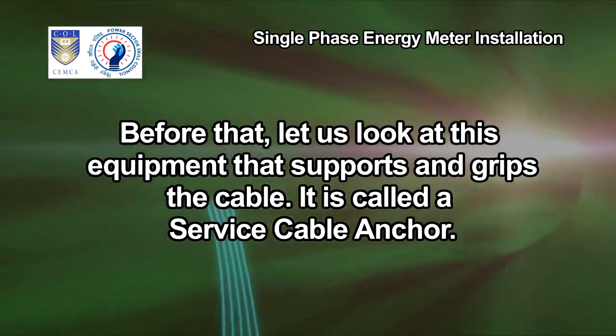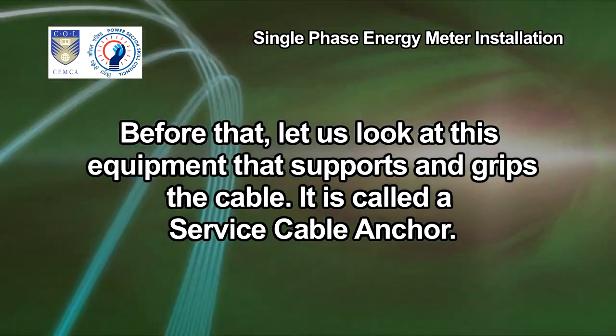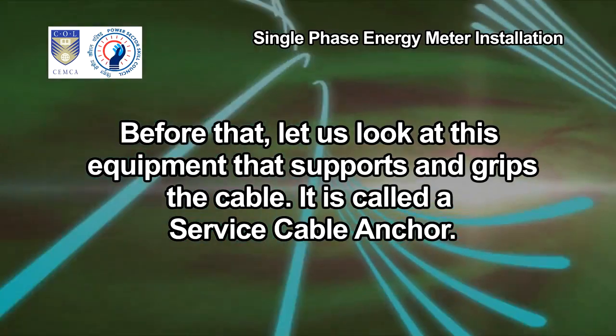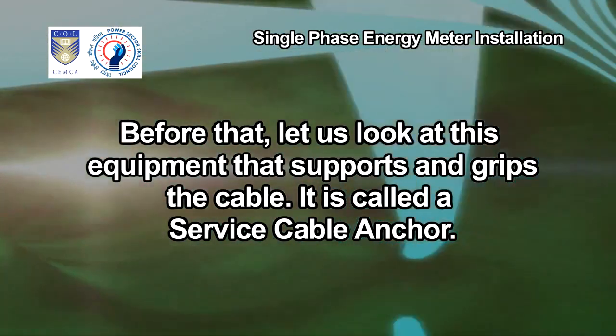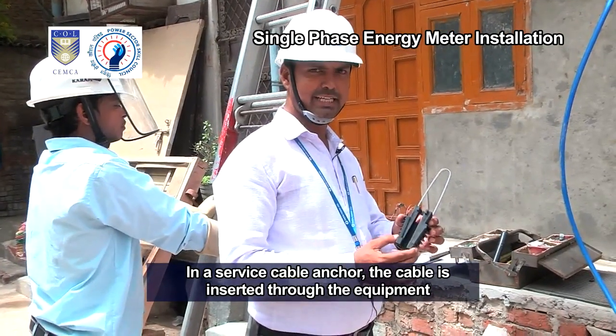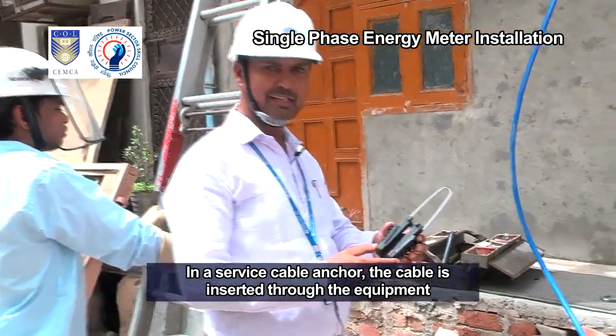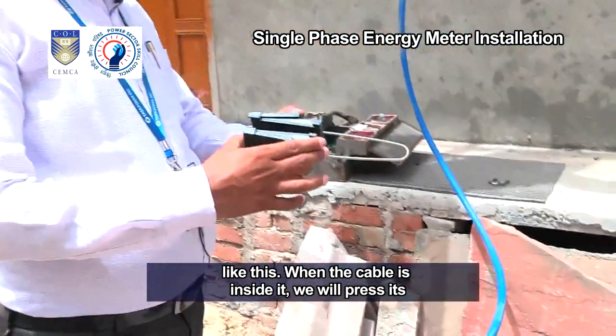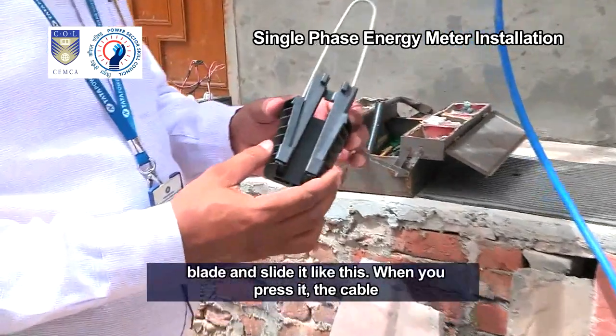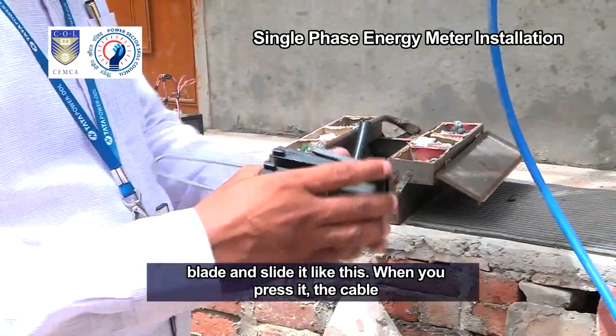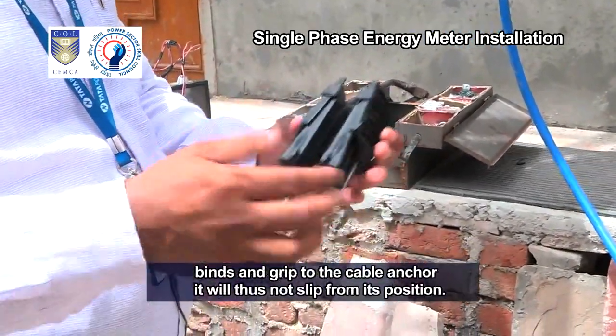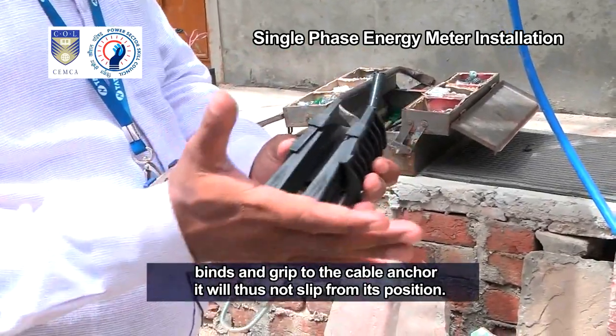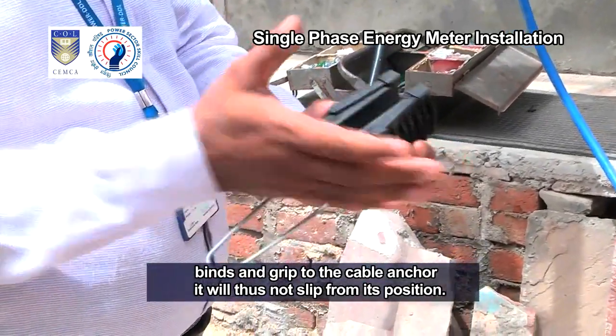Before that, let us look at this equipment that supports and grips the cable. It is called a service cable anchor. In a service cable anchor, the cable is inserted through the equipment like this. When the cable is inside it, we will press its blade and slide it like this. When you press it, the cable binds and grips the cable anchor. It will thus not slip from its position.